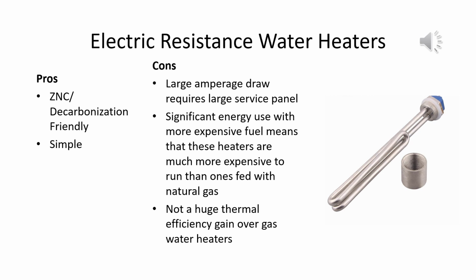Finally, there isn't a huge thermal efficiency gain over gas water heaters. Gas storage water heaters have thermal efficiencies around 80%, and electric resistance storage water heaters have efficiencies around 90 to 95%. So the energy efficiency gain isn't enough to offset the big increase in fuel cost.